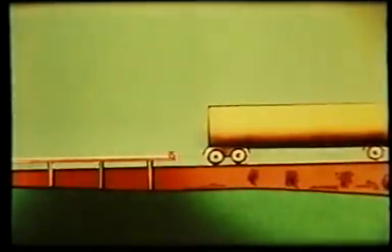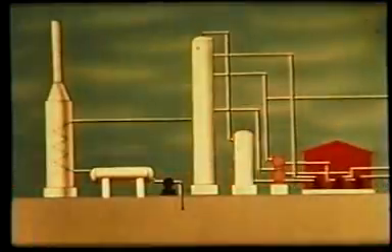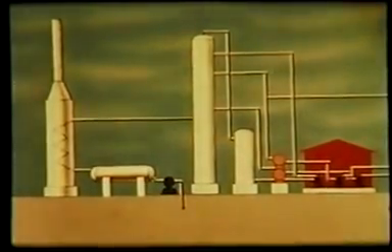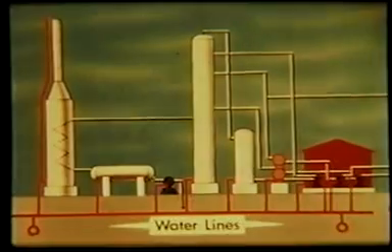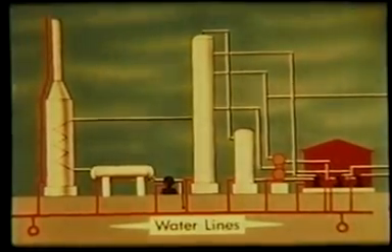Under certain conditions, sparks can occur between insulated objects. When oppositely charged clouds are neutralized by a lightning stroke, their earthbound charges must neutralize themselves. In so doing, they may form an arc between insulated objects or between insulated objects and the Earth. This arcing is one of the reasons why bonding should be used between all machinery, pumps, pipelines, and other conductive insulated materials.